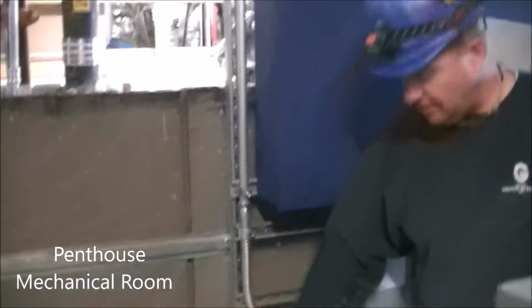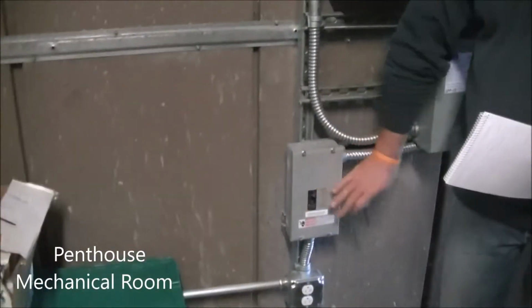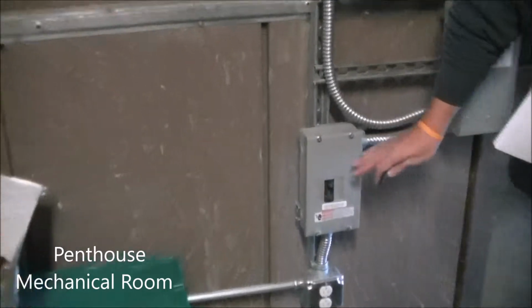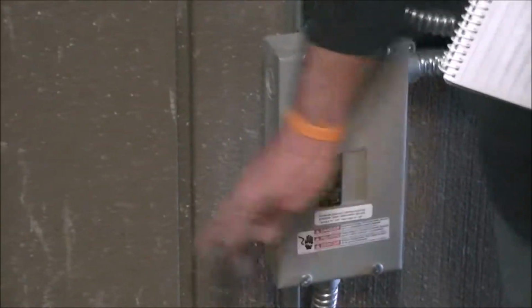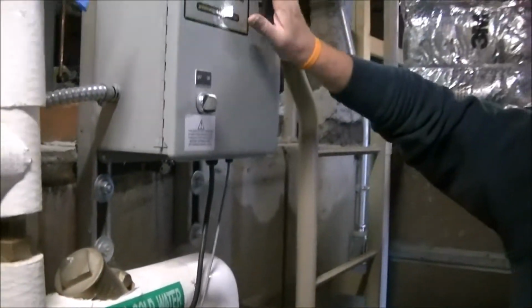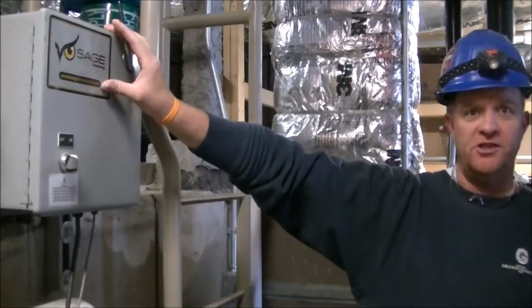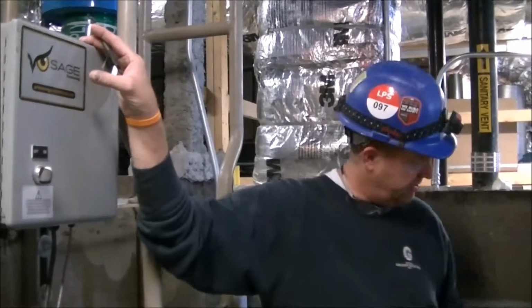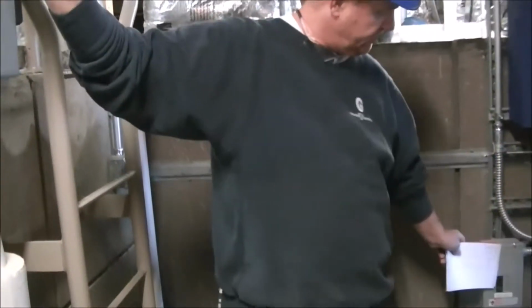Okay. So this little transformer was taken off the high voltage side, so we could step it down to 120 volts, so we could have a couple of outlets around here. I think this is the water monitoring system we put it in for. Basically that transformer there feeds this switch, feeds that outlet, and then feeds that outlet. Which is the master mixing valve? That's it, the mixing valve, yeah.